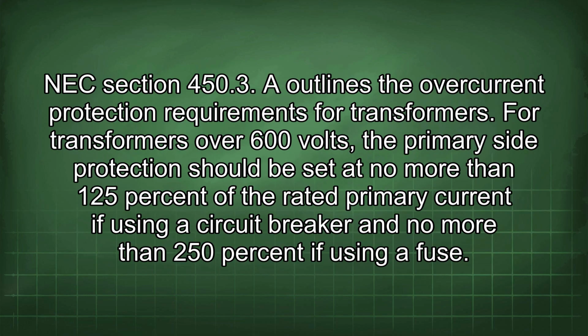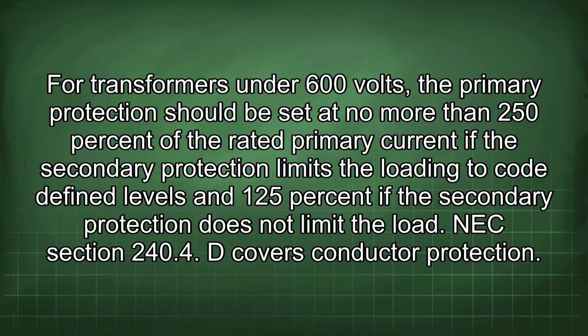NEC Section 450.3 outlines the overcurrent protection requirements for transformers. For transformers over 600 volts, the primary side protection should be set at no more than 125% of the rated primary current if using a circuit breaker and no more than 250% if using a fuse. For transformers under 600 volts, the primary protection should be set at no more than 250% of the rated primary current if the secondary protection limits the loading to code-defined levels, and 125% if the secondary protection does not limit the load. NEC Section 240.4 covers conductor protection.